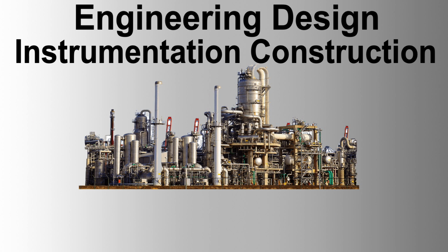Each pair of connections shall be perfectly in line and exactly vertically above each other, thus ensuring a vertical position of the displacer chamber without exerting stress thereon. Displacer level instruments shall be installed initially without the displacer, unless it can be ensured locally that the displacer will not collapse at the equipment test pressure.